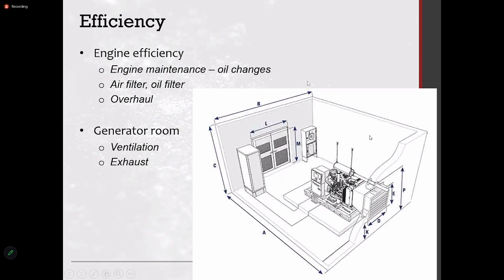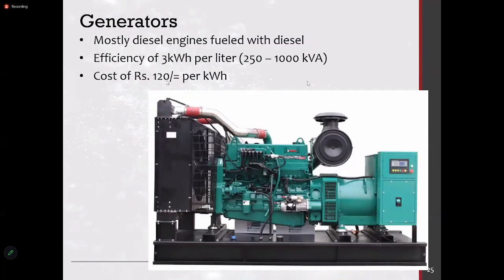So suction air and room space are very important, so that you properly ventilate the generator. And of course, the smoke exhaust is outside and not inside the room space. This is key to the generator room arrangement, to ensure that the generator is running at an acceptable temperature. In addition, you can have room ventilation as well if it is a very big generator, to ensure cooling. Cooling is very important with the generator system, and the water circulation. If it's a radiator system, you'll have water jackets just like a vehicle engine, so look at water levels to ensure cooling happens properly. Ventilation and exhaust are quite critical in generator room and generator efficiency.